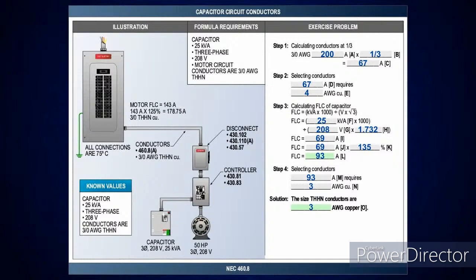True. Okay. And then this is a capacitor. I've got a 25 kVA capacitor. It's three phase, 208 volts, and the conductors are 3 aught. Now, as I look at my 3-aught conductor and I go look at table 310.16, there's two calculations here, and you're going to do it based on the largest calculation. So you can take the conductors at a third. So if I have 3-aught conductors and I look at table 310.16, 75 degrees C column, it's going to tell you a third gives me 67 amps, and 67 amps is going to require number 4 conductor.